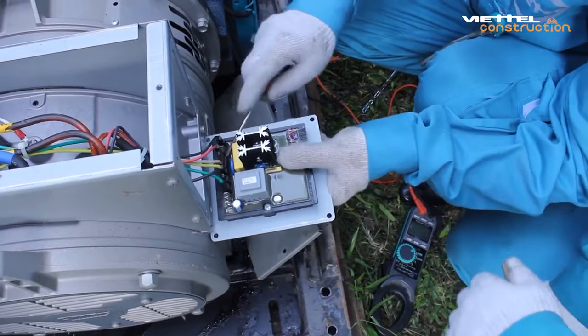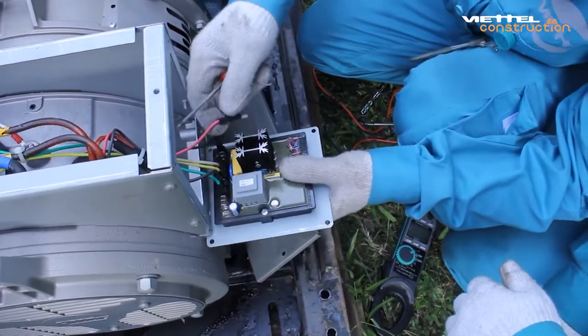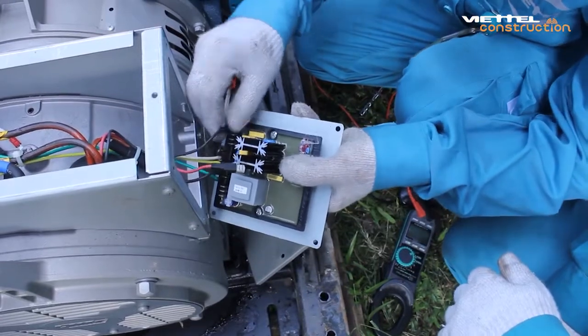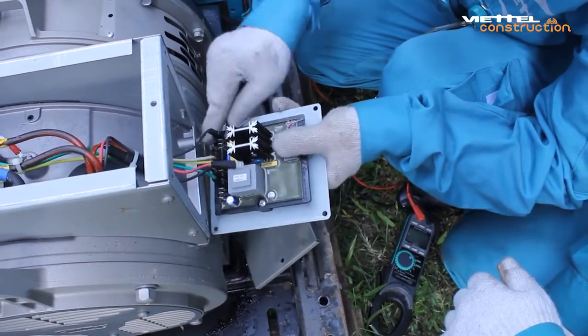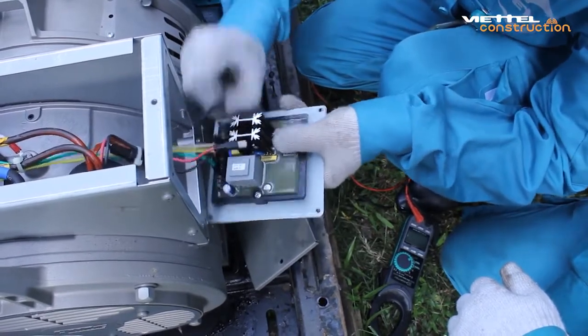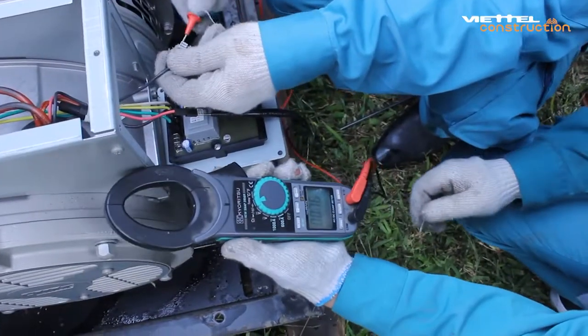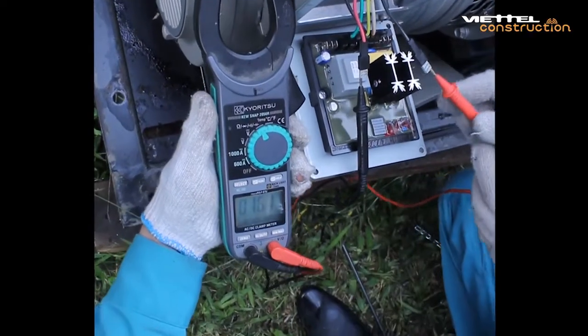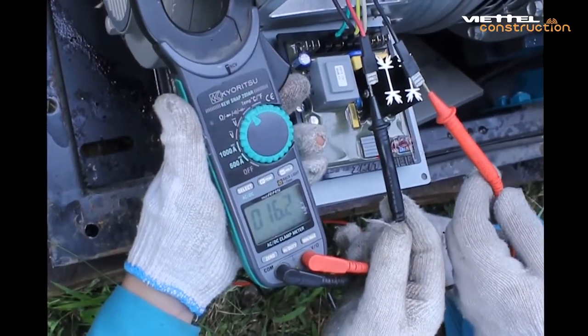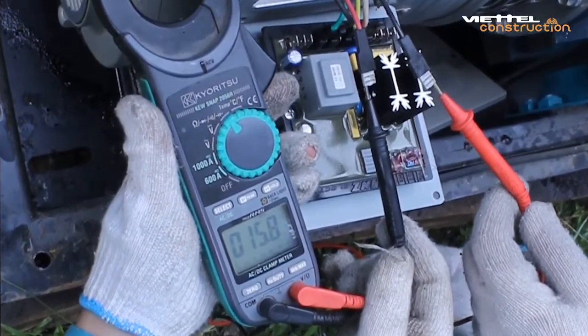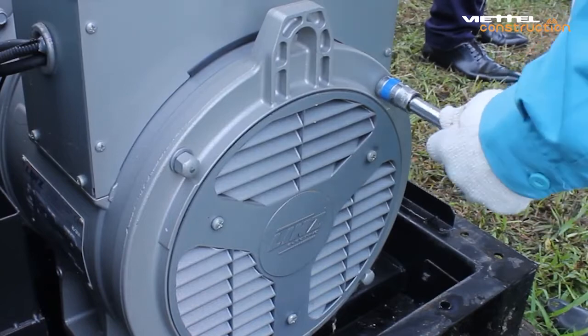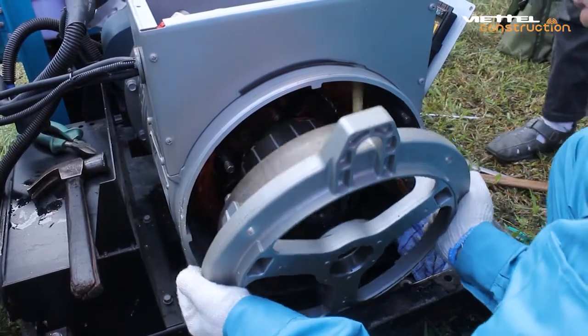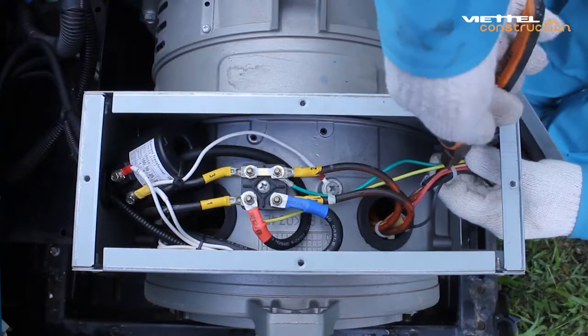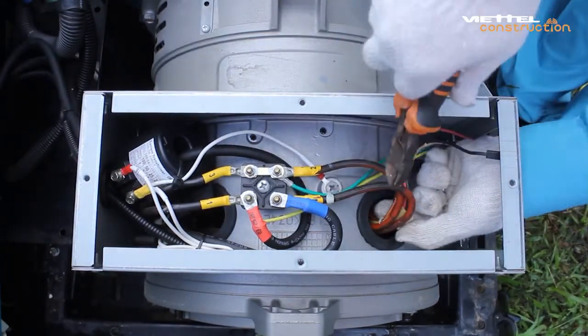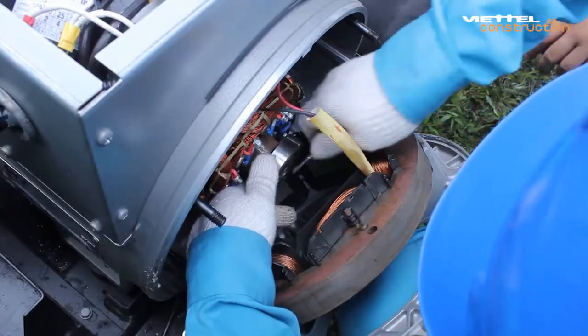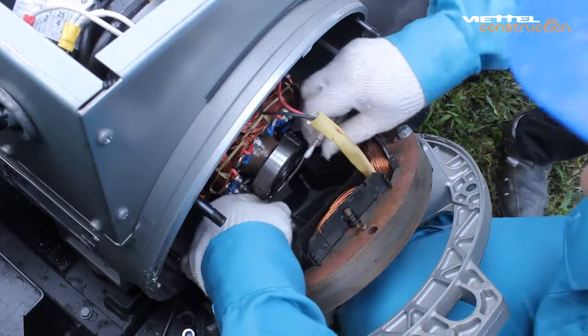Measure the resistance of the excitation coil. It must reach in the range of 10 to 18 ohms. Remove the protective cap of the stator windings. You need to remove the 2 excitation wire from the AVR to avoid breaking the wire. Clean the inside of the coil. Use industrial grease into ball bearing.